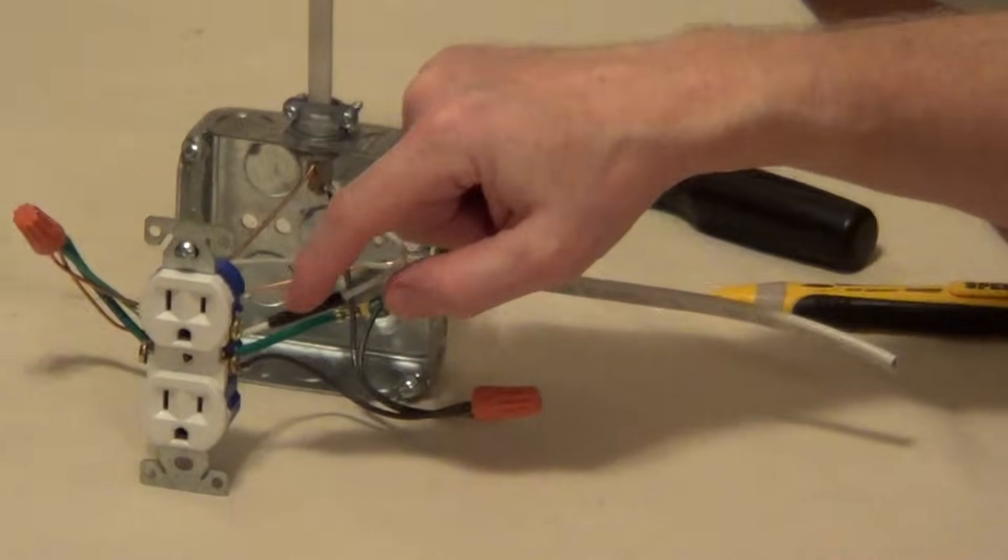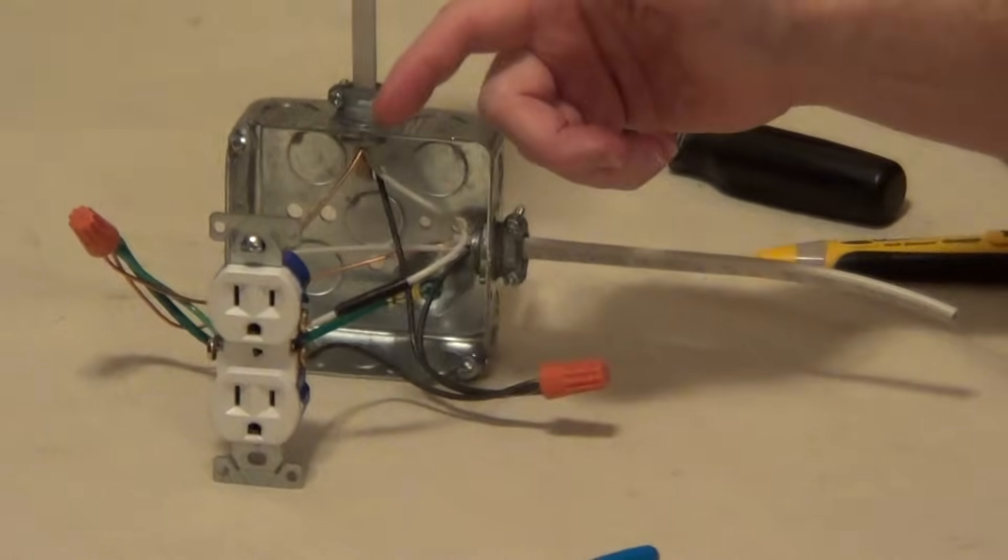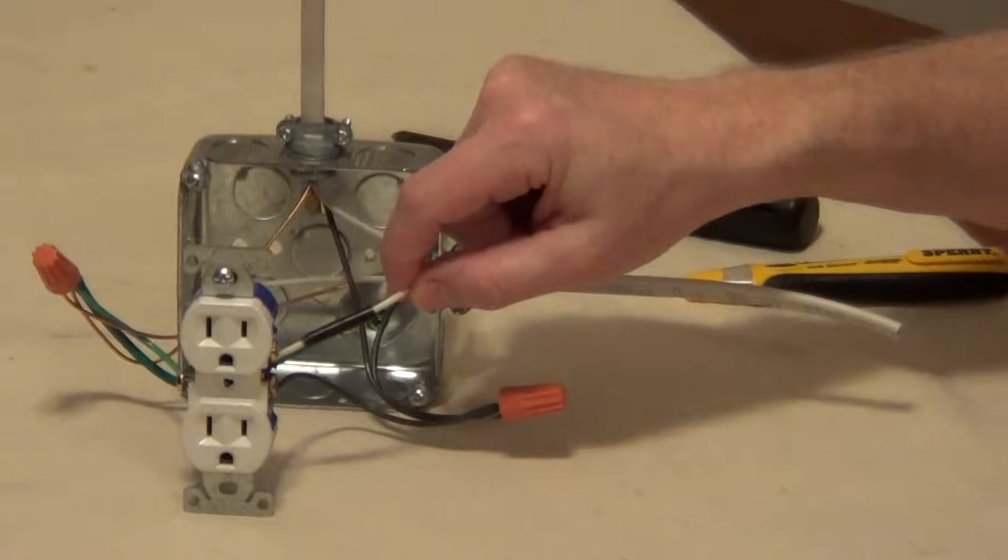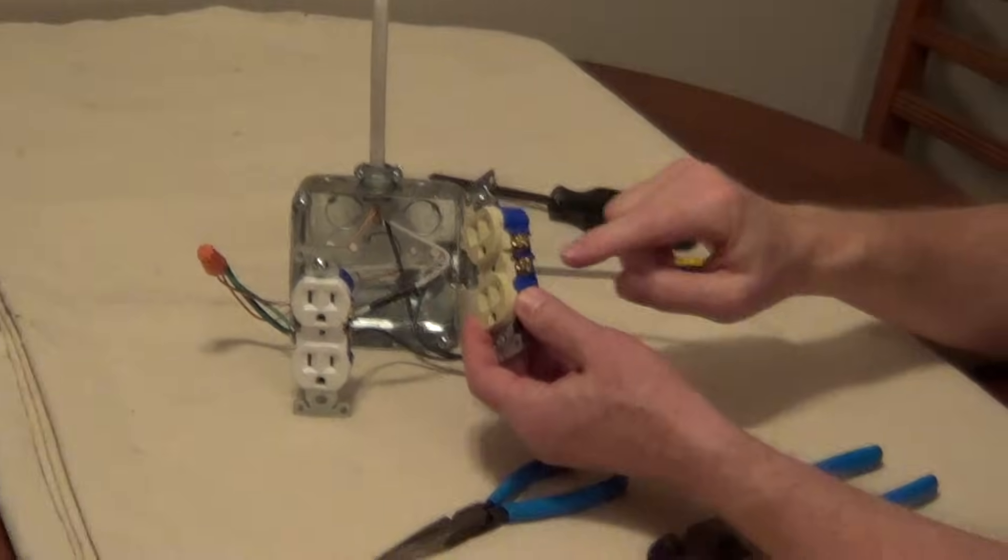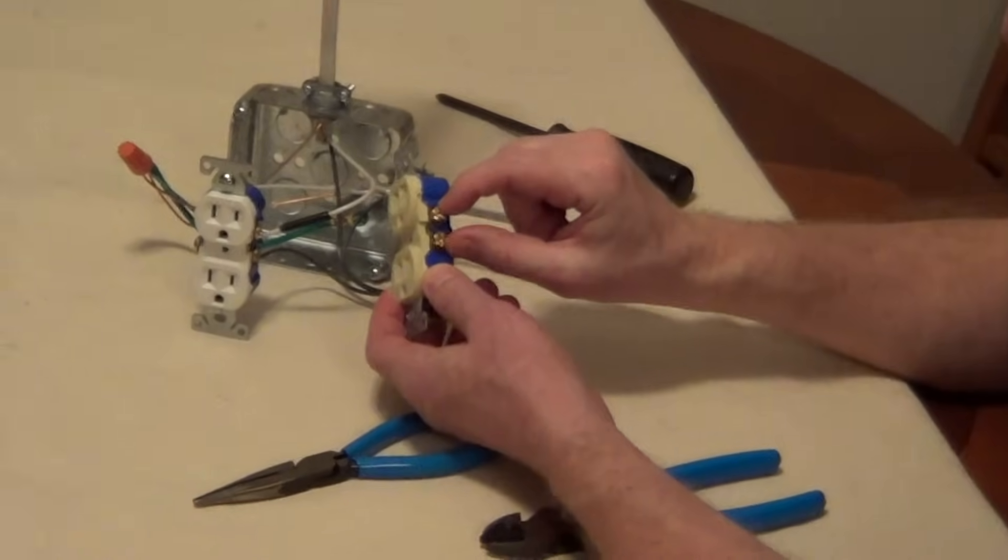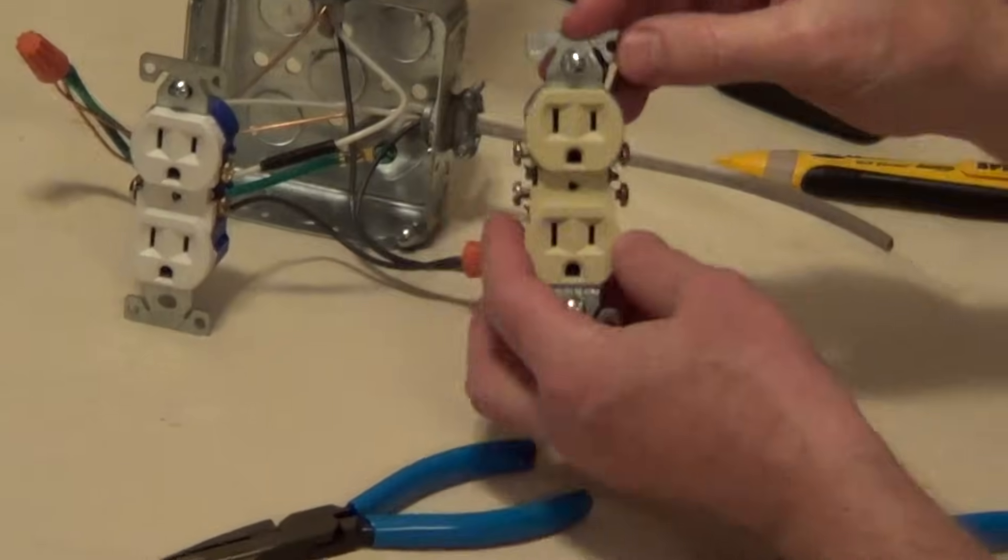And again, we have to mark this white with a piece of black tape or black paint so that everybody knows this is hot. But we can't have both of these screws with hot wires. So what we have to do when we replace this, we're going to turn off the power.